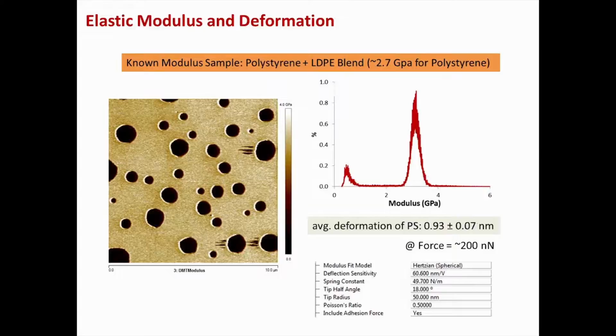Now, how do we make sure that the measurements we are doing are right and it is reporting the right modulus numbers? So Bruker also has some known modulus samples, like polystyrene with some kind of LDPE blend. Polystyrene is known to have about 2.7 GPa as its modulus. So what you do is reference, or calibrate, the tip from these kinds of samples and measure the elastic modulus on them.